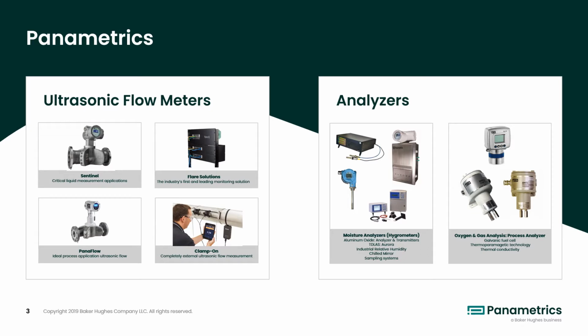Our analyzers start with our moisture analyzers, or hygrometers, which include multiple technologies such as aluminum oxide, TDLAS, relative humidity sensors, and chilled mirrors. These analyzers also come with our standard or custom designed sampling systems designed for proper conditioning of the fluid for the sensors. Our oxygen and gas analyzers include using galvanic fuel cells, thermal paramagnetic, and thermal conductivity technologies. Moisture, oxygen, and hydrogen measurements are critical parameters in the refinery for optimal performance, but unfortunately we will not discuss them in detail during this presentation.